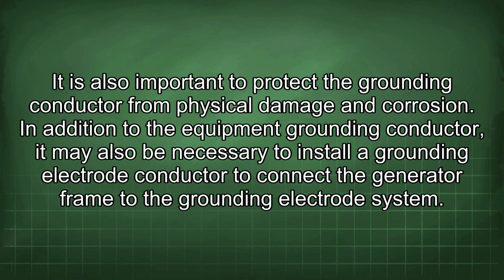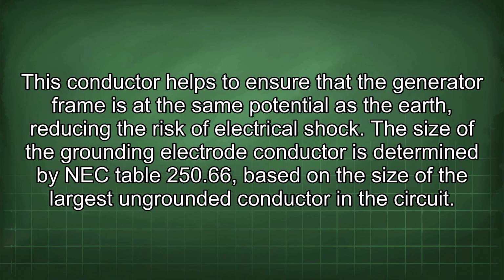In addition to the equipment grounding conductor, it may also be necessary to install a grounding electrode conductor to connect the generator frame to the grounding electrode system. This conductor helps to ensure that the generator frame is at the same potential as the earth, reducing the risk of electrical shock. The size of the grounding electrode conductor is determined by NEC Table 250.66, based on the size of the largest ungrounded conductor in the circuit.